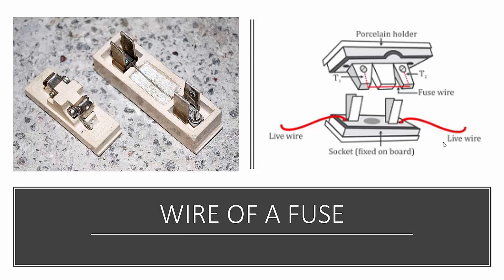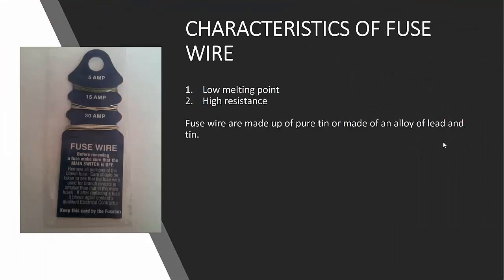A copper or aluminium wire is unsuitable for use as a fuse wire because they have a high melting point. Ordinary copper and aluminium wire must be avoided because it is very thick, so the resistance will be low and it will allow current higher than the safe limit. A fuse wire permits current flow only up to a certain fixed limit called the current rating of the fuse. The characteristics of fuse wire are low melting point and high resistance. Fuse wire is made of pure tin or an alloy of lead and tin. Available fuse wire ratings are 5 ampere, 15 ampere, and 30 ampere.